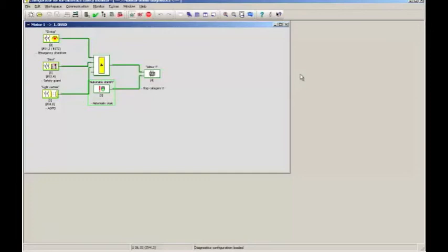So let's check the operation. First thing is I will hit the e-stop, which will shut down motor 1. The e-stop is now red, which indicates it's in the safe state. If I release the e-stop, it turns yellow because I still need to activate my reset function, which is the button I connected to input S72. When I do that, the contactor pulls in and everything starts up.